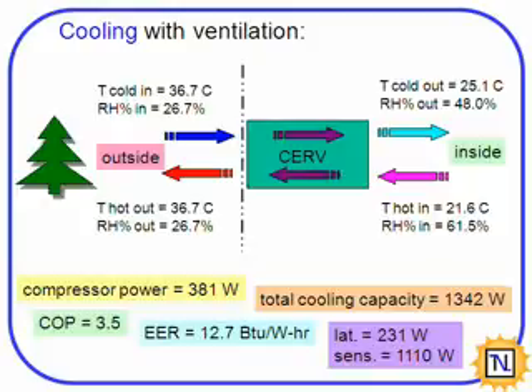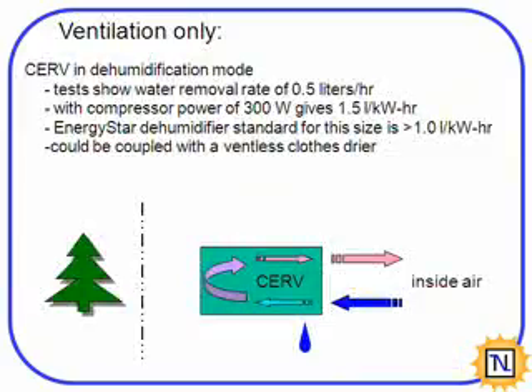Here we see a COP of 3.5, a bit more latent, and then sensible loading there. And then ventilation mode. So it also can be done where the compressor's not on. If the control system sees what's coming into the unit, it can say, hey, I don't need to run the compressor. Or if you purely want to dehumidify the inside air, just shown here, you're just running this over the evaporator, dropping moisture out.